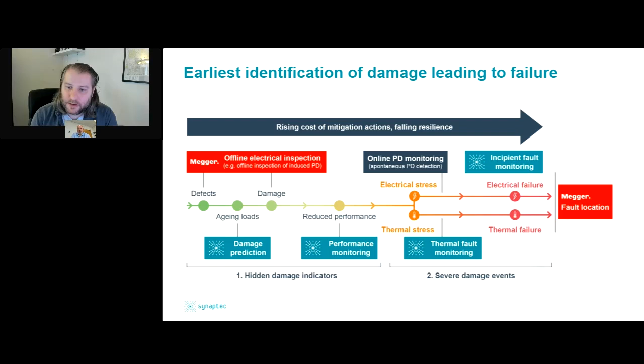So very often we'll find, obviously, best practice with Megger test equipment during commissioning of a cable, that's vital. As Stephen alluded to earlier on, what tends to happen is that immediately thereafter, once you've energized the cable, you've got that instantaneous validation that all of those screen currents are correct and as planned, and you've got correct bondings and earthings, everything's working as expected while your contractor is even still on site. So that's the message about helping people with more confidence in the commissioning process.